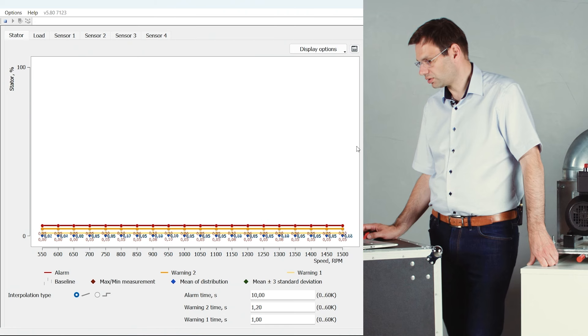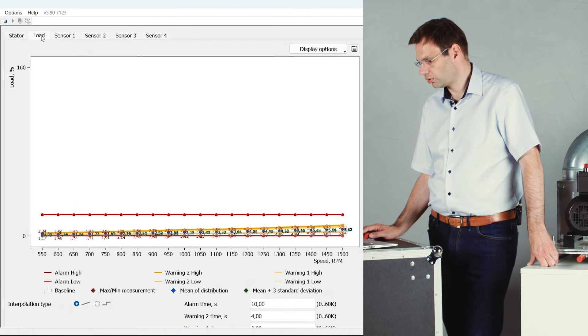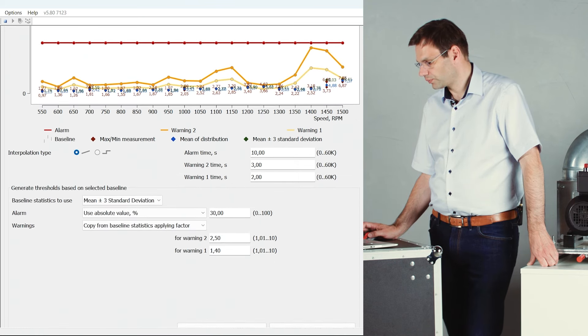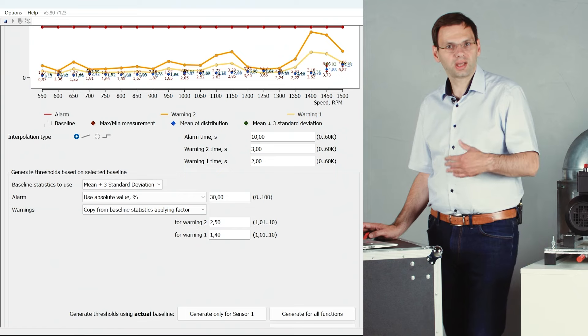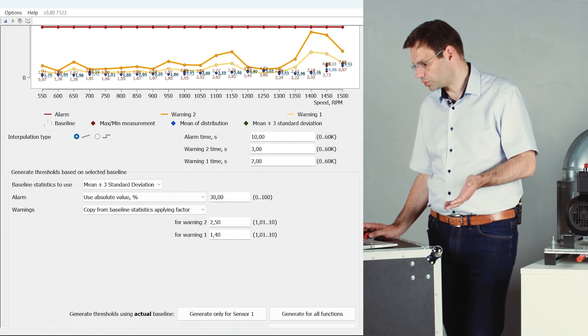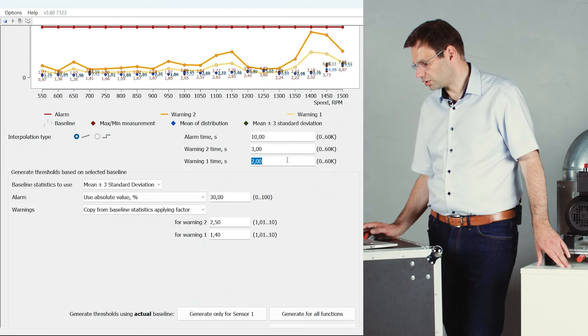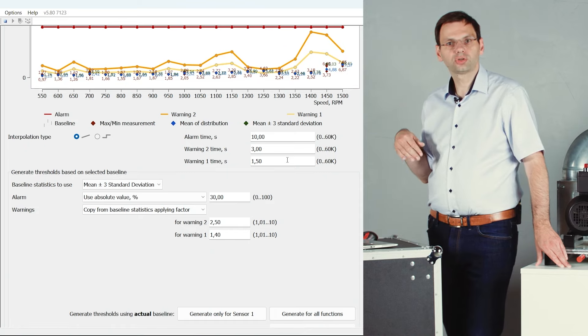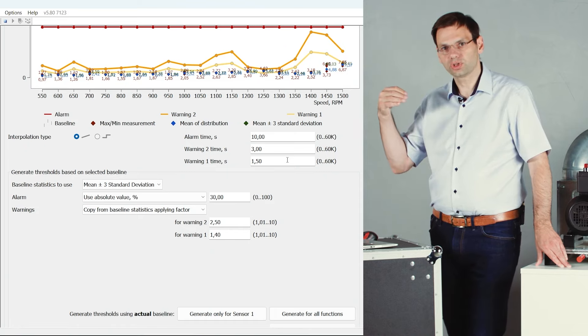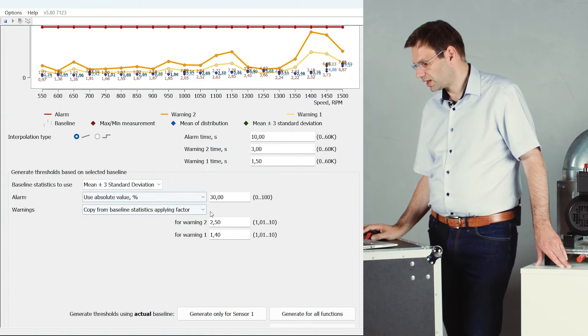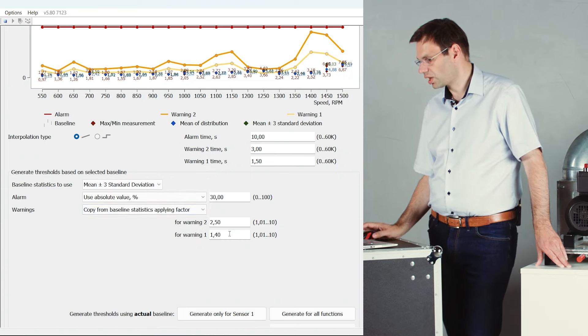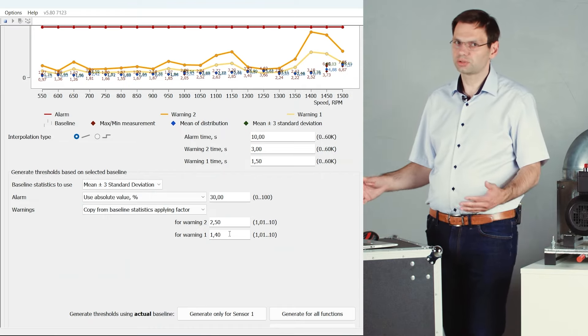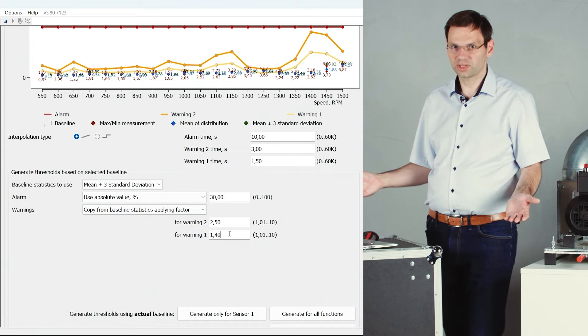I can see here the values for the stator, for the load, and for my vibration sensor. If I want to make adjustments, I can adjust the reaction time — how fast the system should react to a monitored value which exceeds a threshold. I can also adjust the distance between the threshold and the baseline. For most applications, default values are fine and we can proceed to the next step.